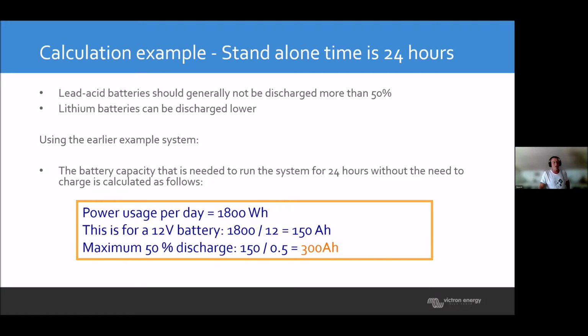If we're talking about lead-acid batteries, the normal discharge level is around 50%, and you don't want to go lower, because you'll destroy the battery really fast if you go down to heavy deep discharges. That means the 150 amp hours will go to 300 amp hours instead, to account for that 50% level.